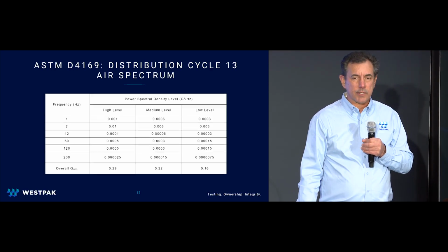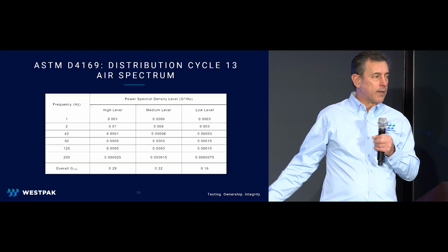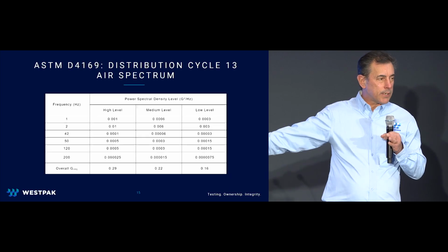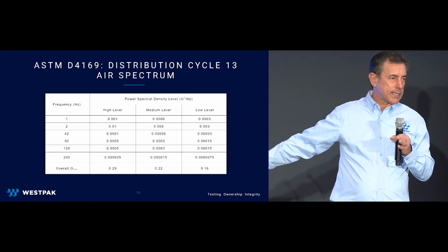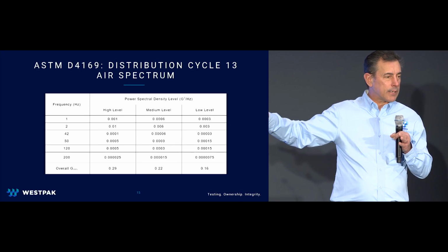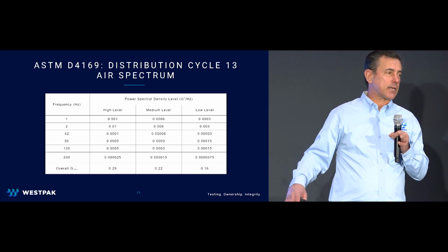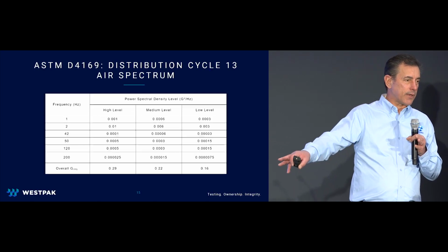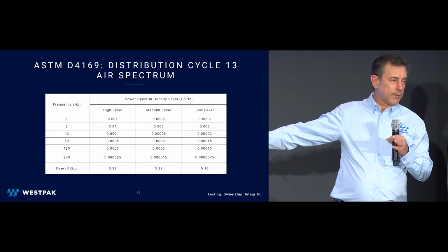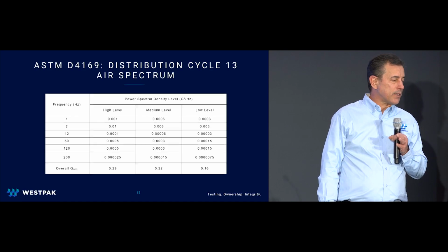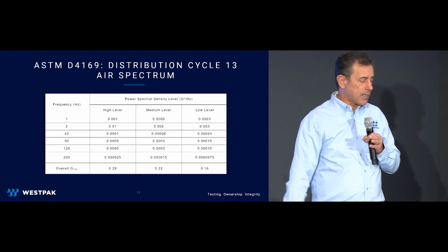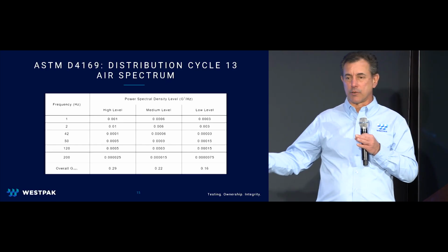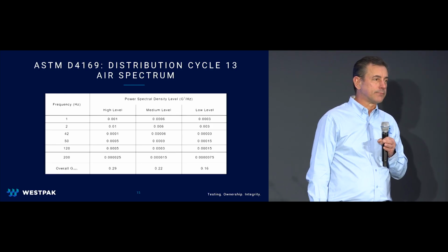So are there any questions regarding any of this here? I kind of gave you the justification for using this standard. You don't have to retest because the intensity is a lot lower than previous testing. I know all of you have tested already to even assurance level 2 of the air spectrum. This is even lower than that. So you can write your justification for the use of this, and there isn't any gap because there isn't anything that changed significantly that would adversely affect your products. Any questions?